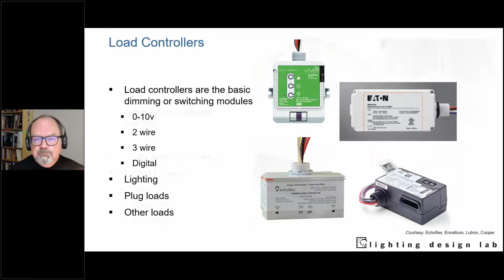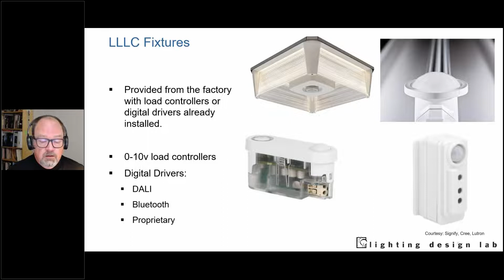Or you can have other options that communicate in a variety of different ways. They'll be available for the communication protocols we talked about: 0 to 10 volt, or in some cases DALI, DMX 512. They may have 2 wires or 3 wires connecting to them depending on the protocol. They'll either be for dimming or switching lighting, or for larger 20 amp devices for plug loads. Some might be UL924 devices. Then we have LLLC light fixtures, where basically everything is in the fixture itself rather than having separate parts and pieces. You're still going to have switches and other devices, but these all come together.